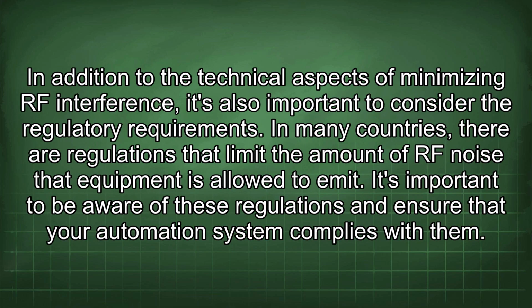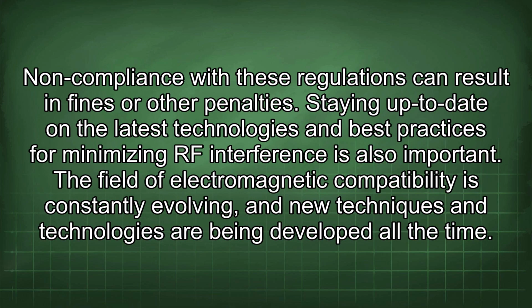In addition to the technical aspects of minimizing RF interference, it's also important to consider the regulatory requirements. In many countries, there are regulations that limit the amount of RF noise that equipment is allowed to emit. It's important to be aware of these regulations and ensure that your automation system complies with them. Non-compliance with these regulations can result in fines or other penalties.